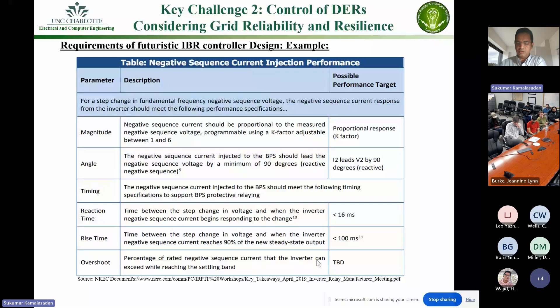This is a requirement developed based on NERC guidelines for current injection or current support requirements from IBRs, basically during unbalanced conditions and fault conditions where we have injection from IBRs and negative sequence current operations. There are a few others, for example the UK grid code, and other grid codes around the world, which include magnitude, angle, timing, reaction time, rise time, overshoot - all control related aspects. It's important to have this included on the inverter-based resources.